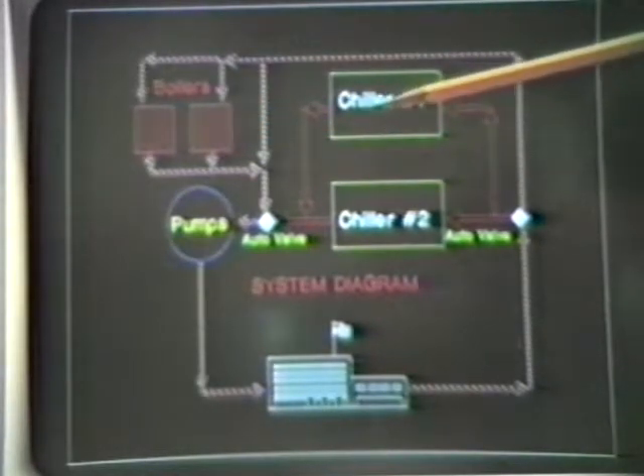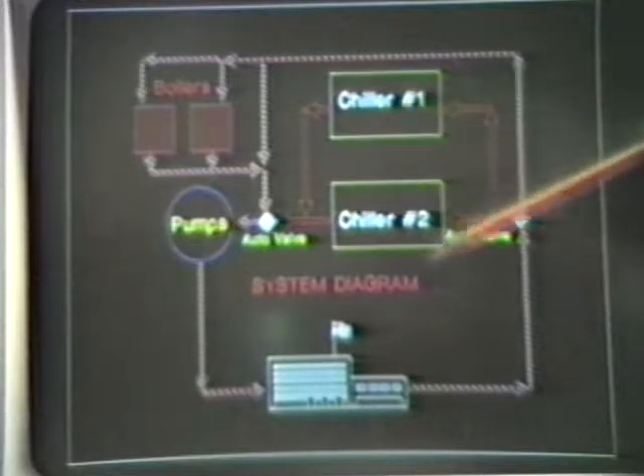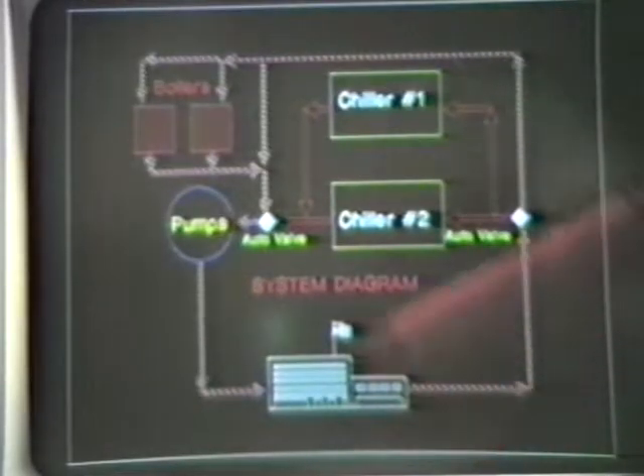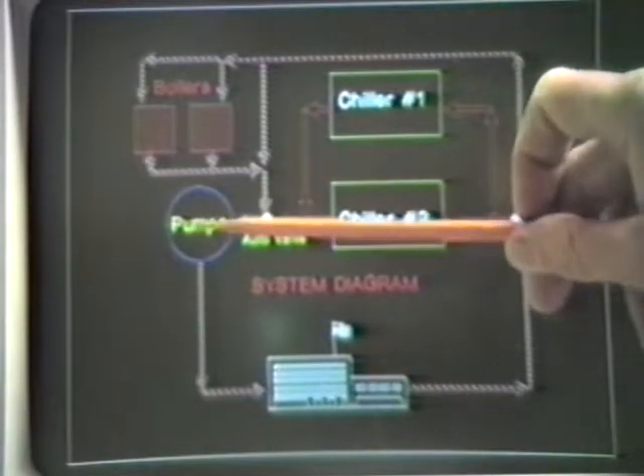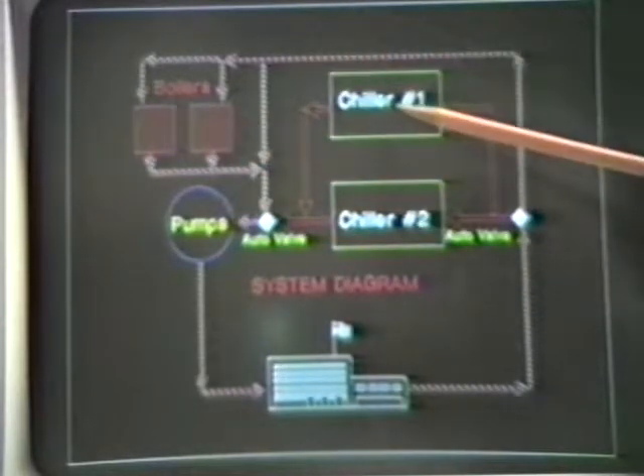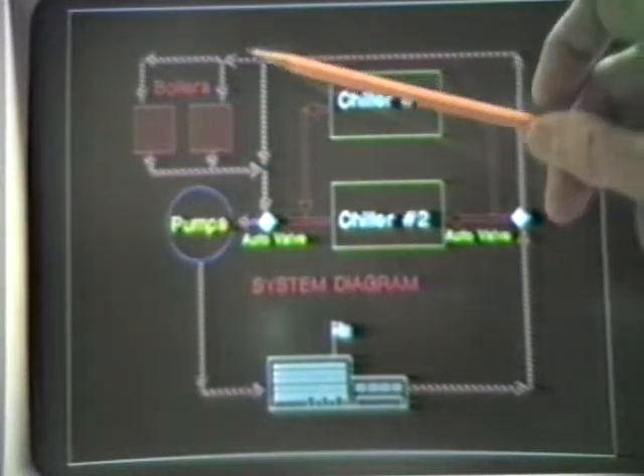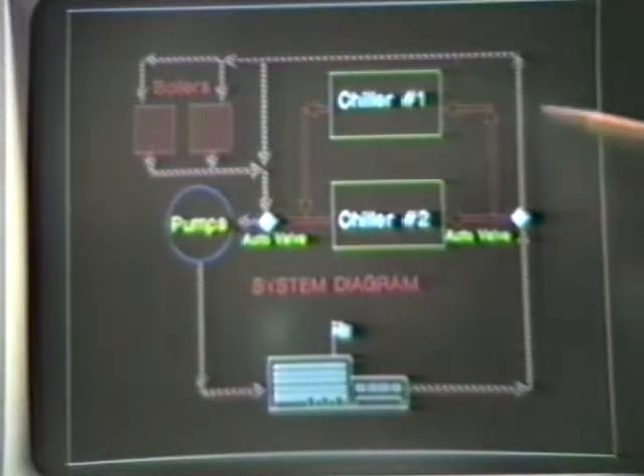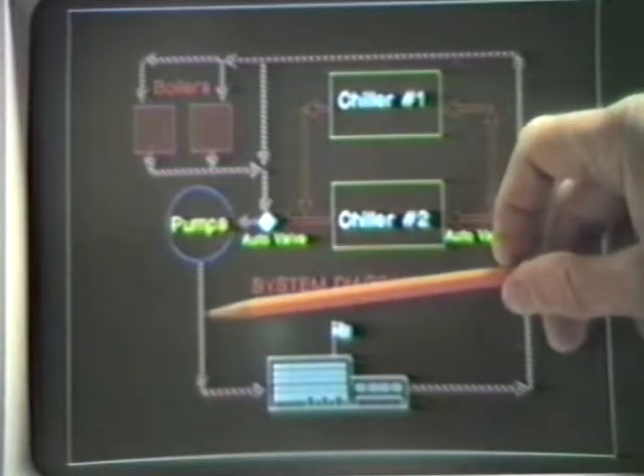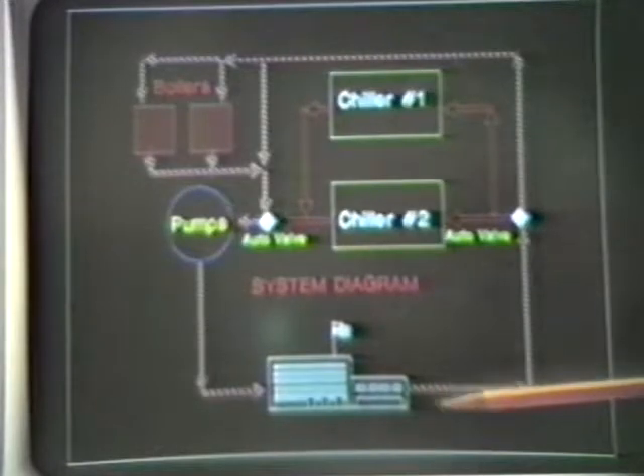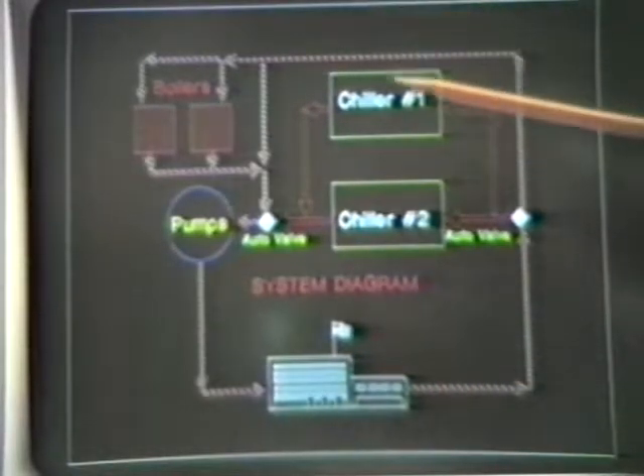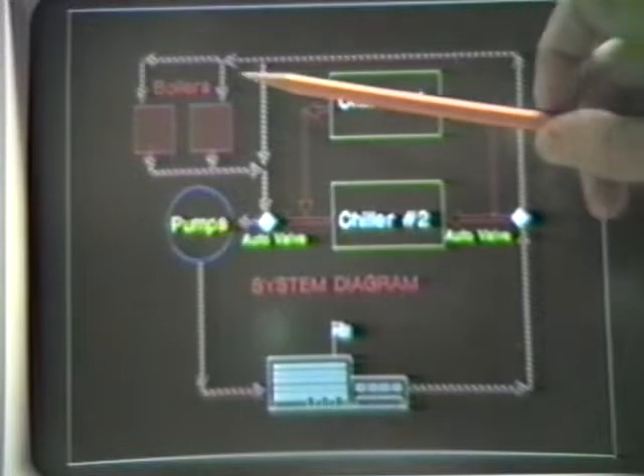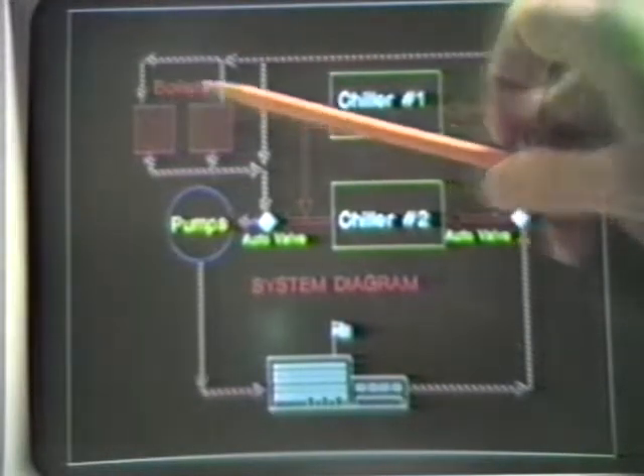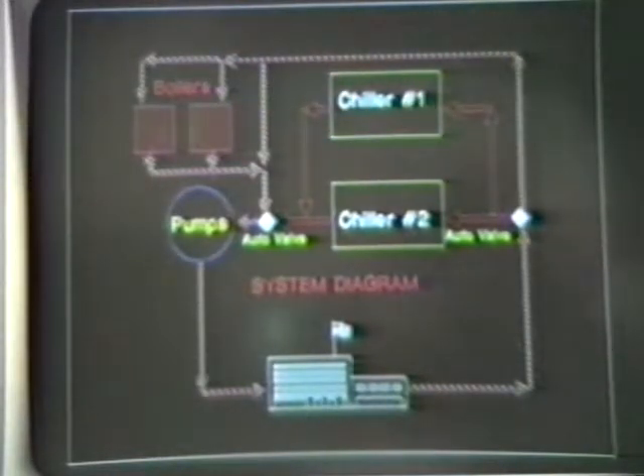There should be enough time given, and we recommend at least a day, 24 hours of continuous pump running without either the boiler being fired or the chillers being on, to allow the water temperature to neutralize and settle out before we go to the control panel and push either the enable chiller switch or the enable boiler switch. When that is done, the valves will automatically change from cooling to heating depending on which mode is selected.